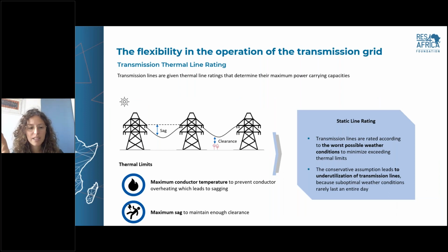Another interesting aspect is, okay, instead of building new infrastructure, we could improve the operation of the infrastructure we already have. You may know that transmission lines have a thermal line rating. That is, I can make flow a maximum amount of current on the line, because if I overcome the thermal limits, the conductor will have a temperature that is too high, and it will have a sag that is so wide that it will not respect the minimum clearance with the ground. It will cause short circuits.